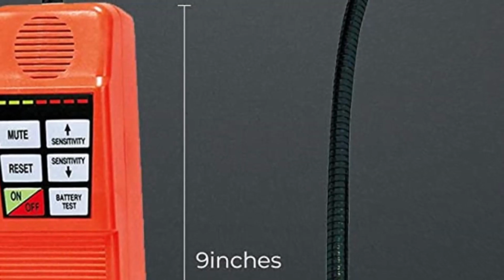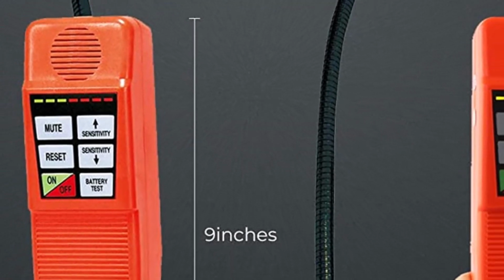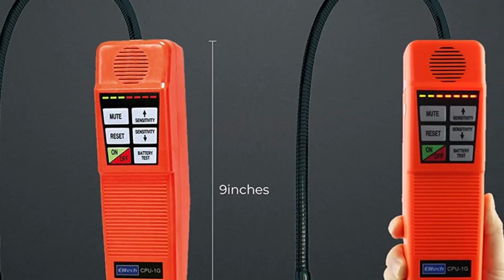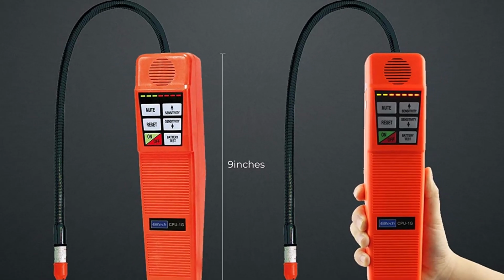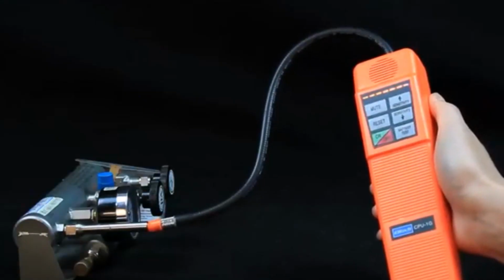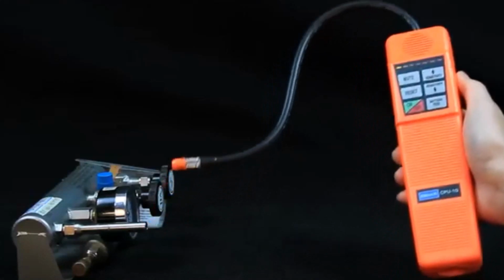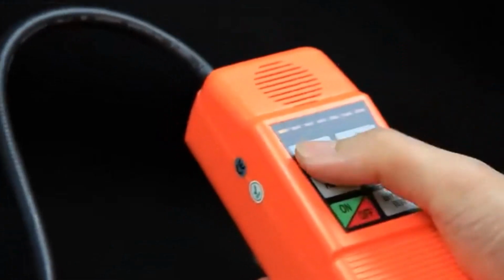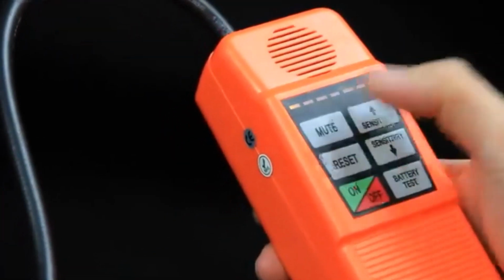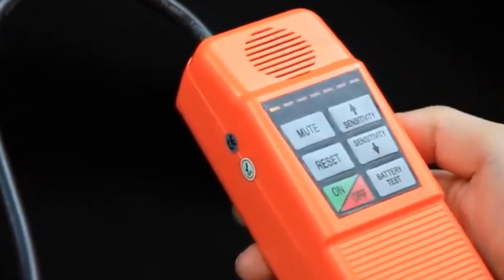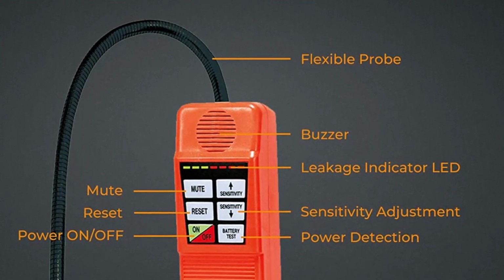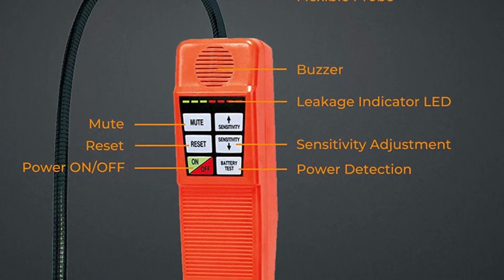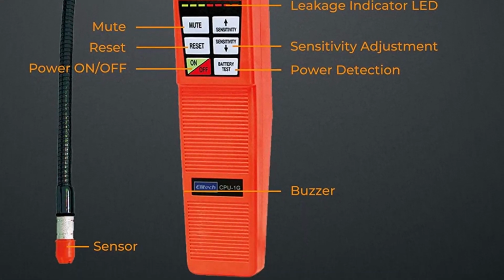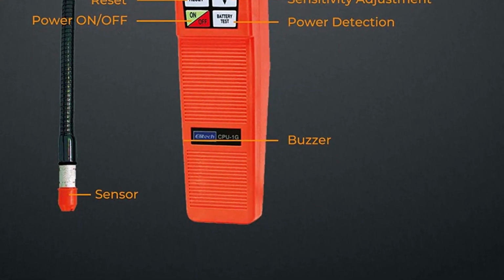One of the significant advantages of the Elitech CPU-1G is its compatibility with various halogen gases used in HVAC systems. Whether you're dealing with R22, R410A, or R134A, this leak detector can accurately detect leaks, making it a versatile tool for professionals working with different refrigerants. By using the Elitech CPU-1G, professionals can streamline their troubleshooting process and minimize costly repairs.